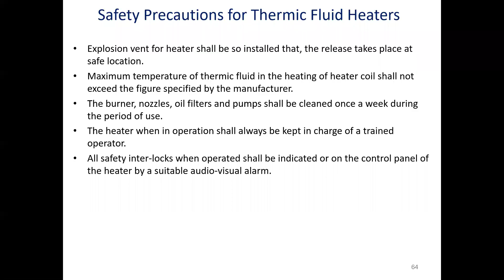Then the burner, nozzles, oil filter, and pump shall be cleaned once a week during the period of use. The heater, when in operation, shall always be kept in charge of a trained operator, and all safety interlocks, when operated, shall be indicated on the control panel of the heater by a suitable audio visual alarm. So these are the safety guidelines or the safety precautionary measures for this thermic fluid system.